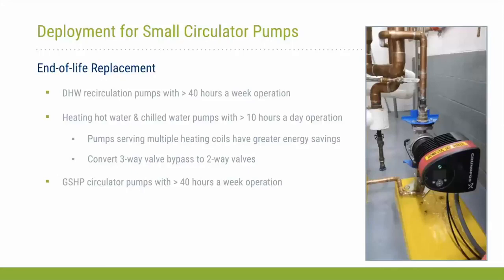For these little pumps that serve multiple coils, you should also have better savings. If I have a circulator pump that serves, let's say, 6 radiant baseboard heating coils, I'm going to have a larger fluctuation in flow rate, and I'm going to need to keep that pump on during the operating hours to meet those loads. So I would look for applications where a single pump serves multiple heating or cooling coils. And then we're also estimating that the circulator pumps could be a good fit for ground source heat pump systems.